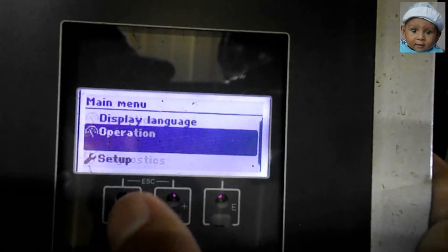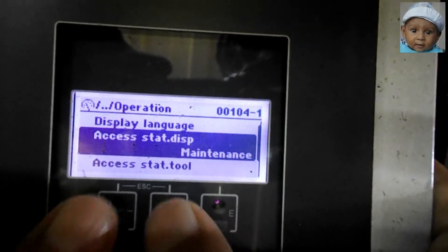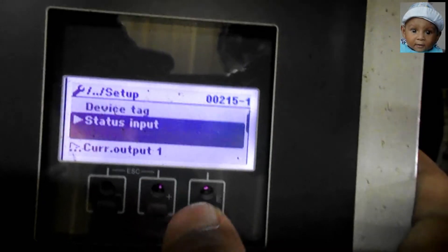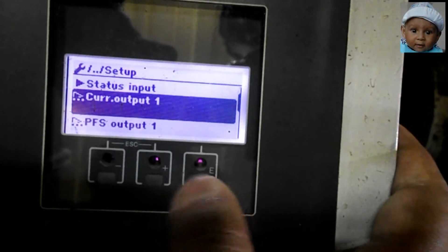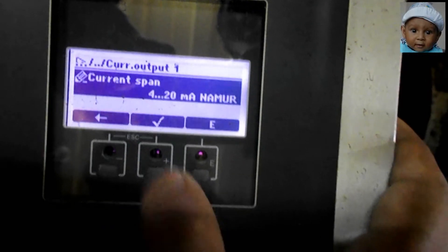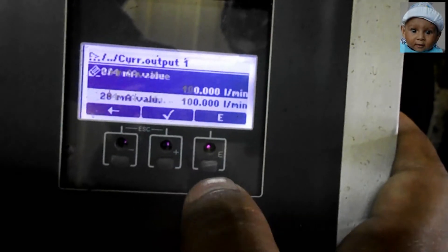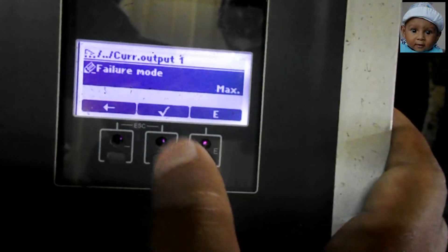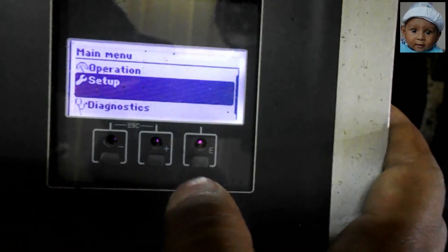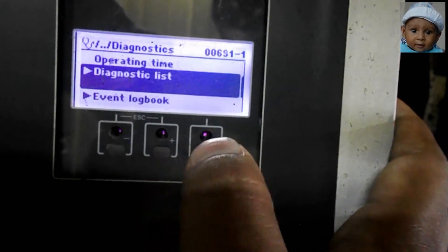The important parameter is how we can set the 4 to 20 milliampere signal according to flow. First, go to Setup, then Current Output 1. I have selected Assign Current as Volume Flow and the volume flow unit is liter per minute. At 0.00 liters per minute it will give 4 mA, and at 100 liters per minute it will give 20 mA signal to the PLC. You can set your required signaling values in this parameter.